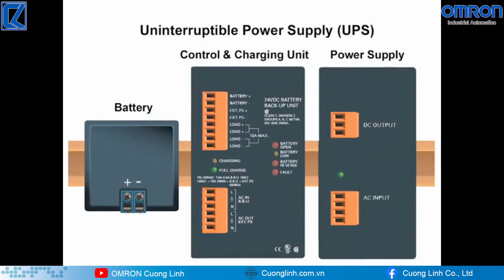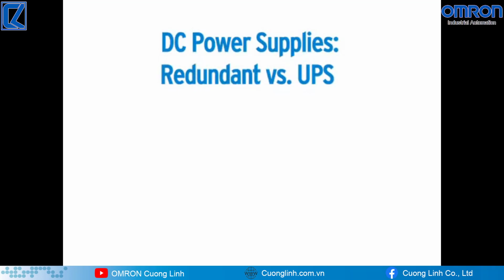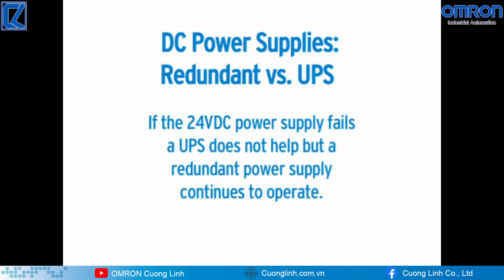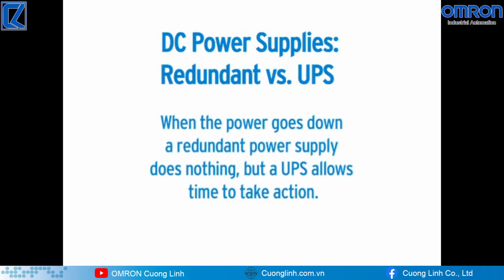I'm going to discuss the installation and use of a redundant power supply system versus a DC UPS (uninterruptible power supply) system. Both serve a purpose in an industrial control panel. If the 24-volt DC power supply fails, a UPS does not help, but a redundant power supply continues to operate. However, when the power goes down, a redundant power supply does nothing, but a UPS allows time to take action.